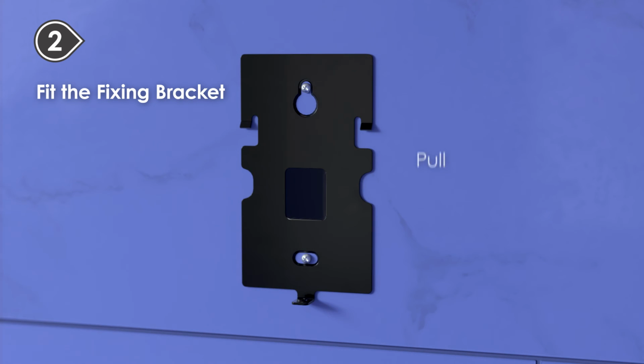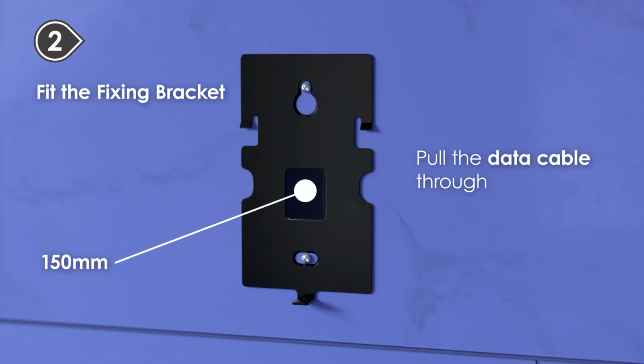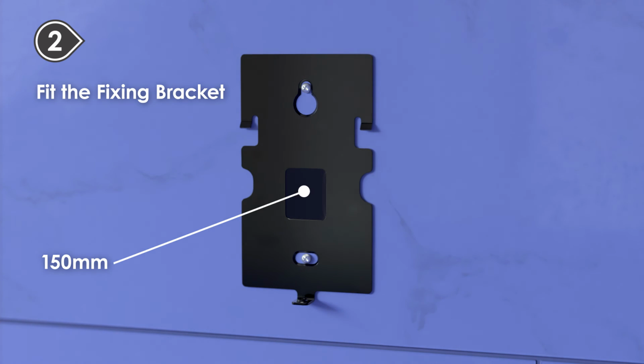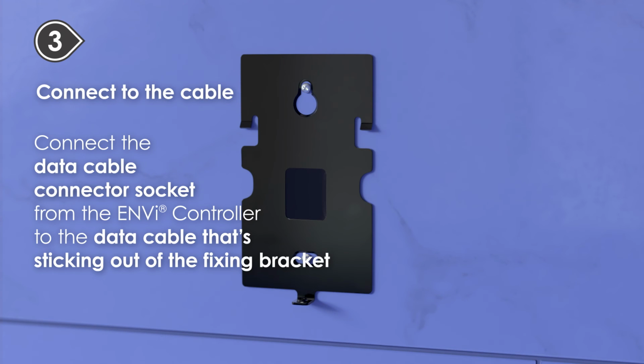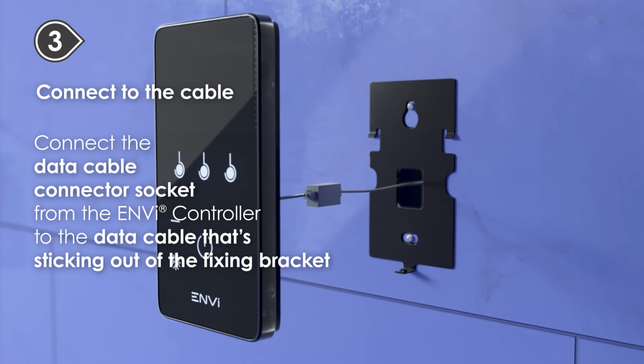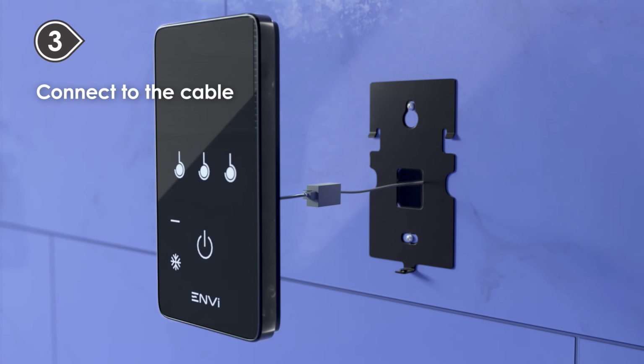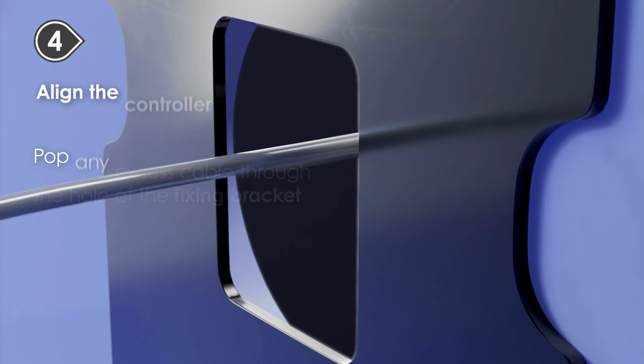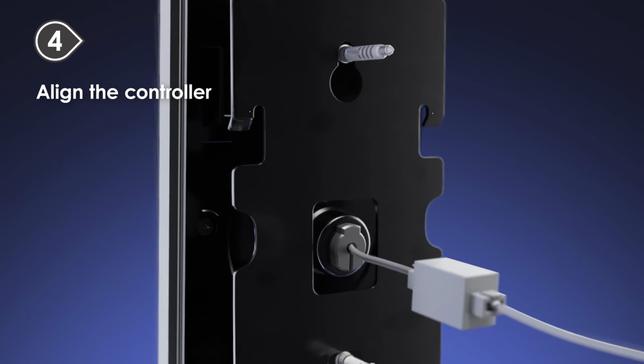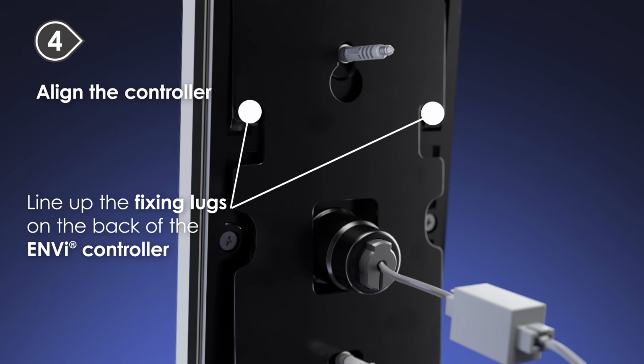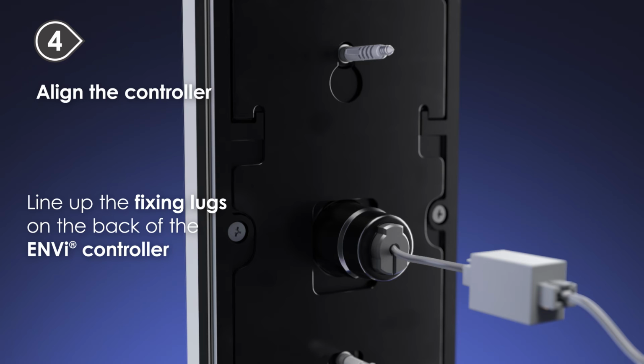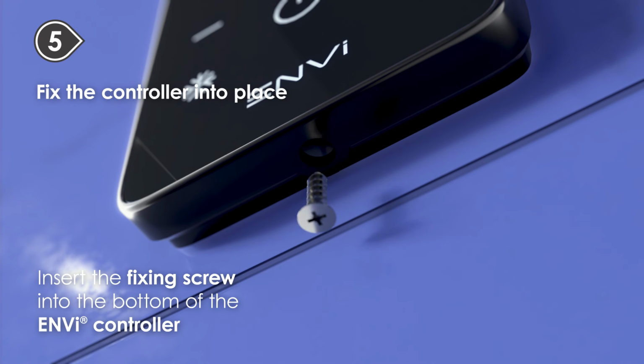You also need to pull the data cable through so that roughly 150mm of it protrudes from the wall for easier connectivity. Connect the data cable connector socket from the ENVi controller to the data cable that's sticking out of the fixing bracket. Take care not to damage the locking tab of the data cable connector. Pop any excess cable through the hole of the fixing bracket so that it goes back into the wall cavity. Line up the fixing lugs on the back of the ENVi controller with the lugs on the bracket, then offer it up to the bracket before sliding it upwards to engage the fixing lugs. Insert the fixing screw into the bottom of the controller and tighten it without over-tightening.